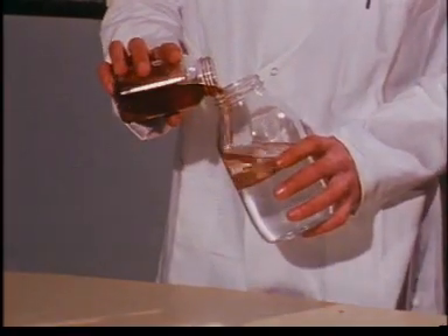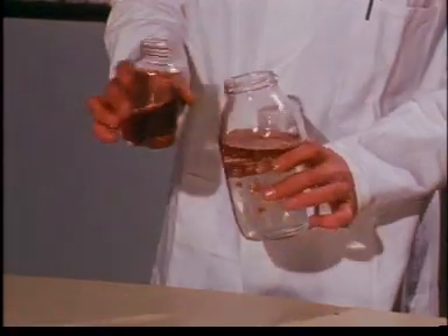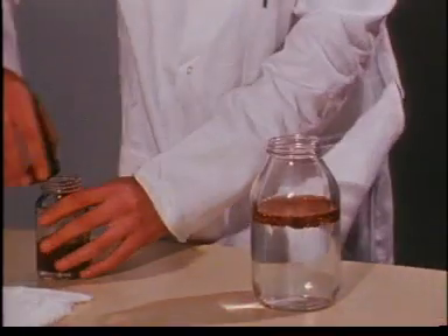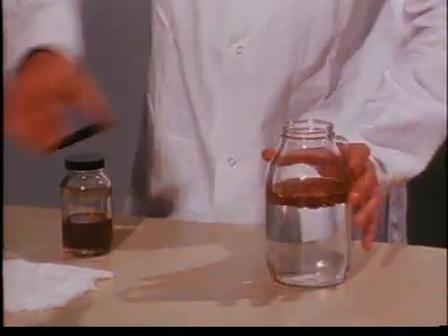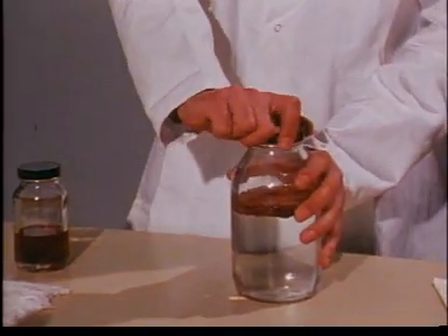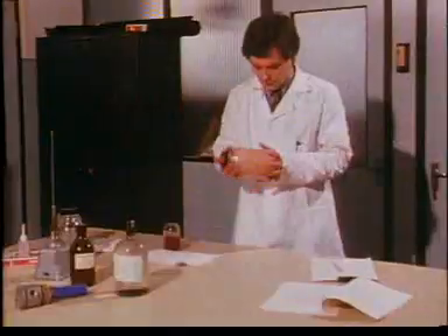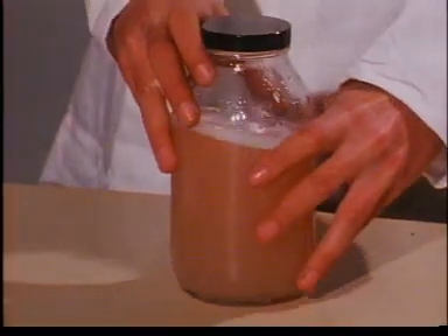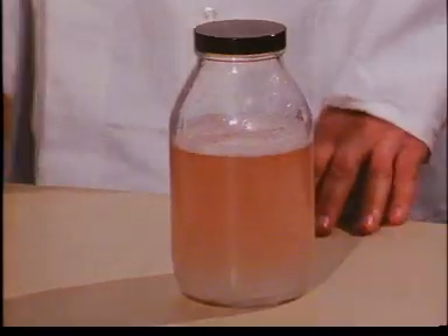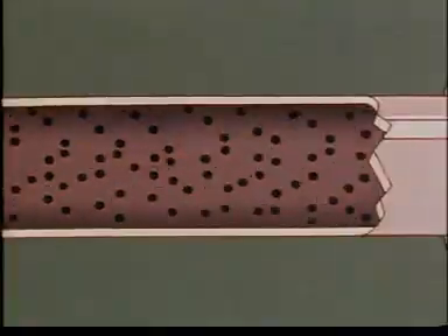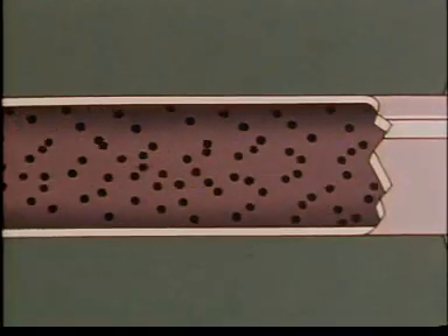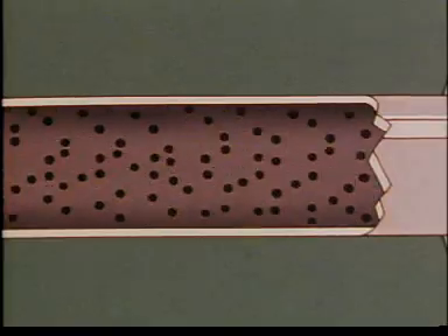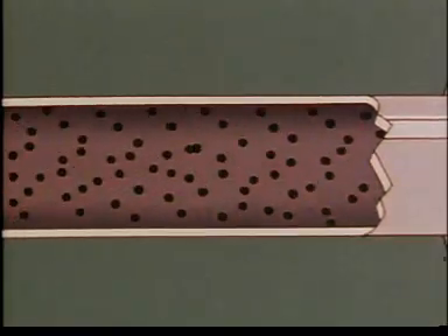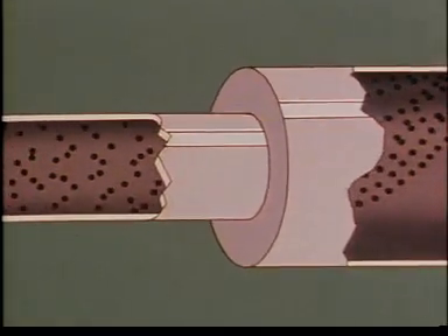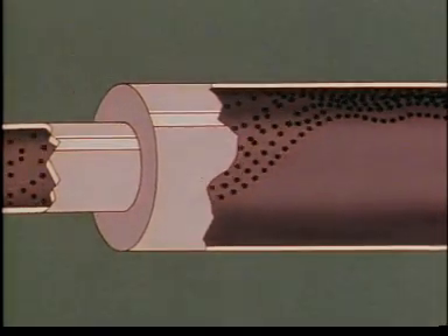The basic principle of oil-water separation is the difference in specific gravity of the two liquids. If oil is poured into water and lightly mixed, the oil will float to the top, leaving clear water below. Depending on the type of oil, this separation can sometimes take place quite rapidly. But if the mixed liquids are in rapid motion, the turbulent flow in a pump or relatively small bore pipe could make separation more difficult. If the speed of the flow is reduced by, say, increasing the bore of the pipe considerably, separation starts and oil accumulates at the top.